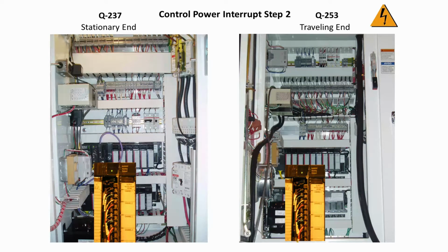If both the number 5 LEDs are on, check both of the output wire numbers for 120 volts at CR1 and CR2 relays. Wire number X2 is the neutral wire. If you have 120 volts on both output wire numbers and either CR1 or CR2 is not engaged, then replace the one that is not engaged.